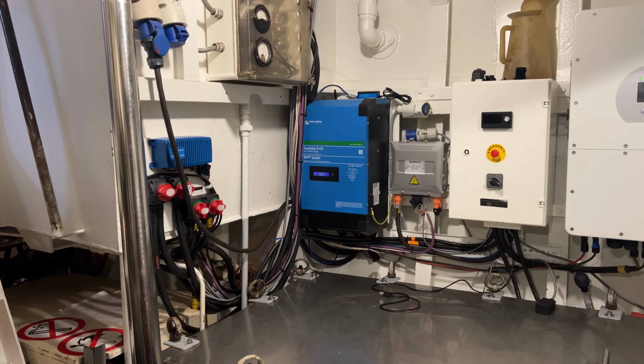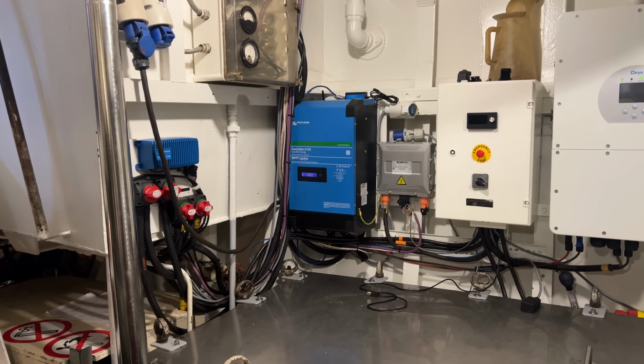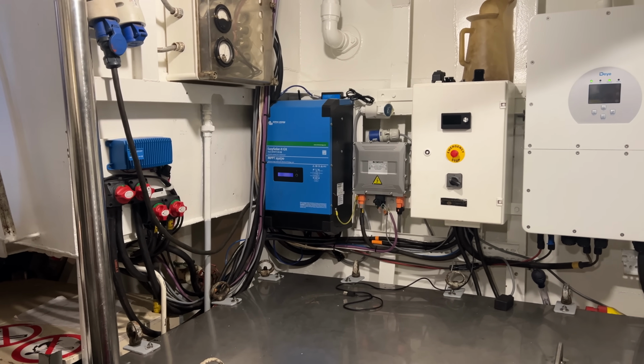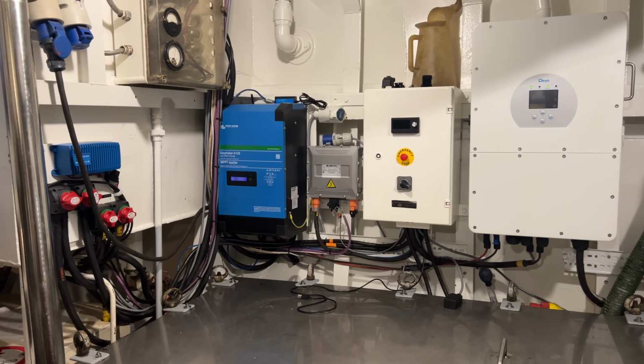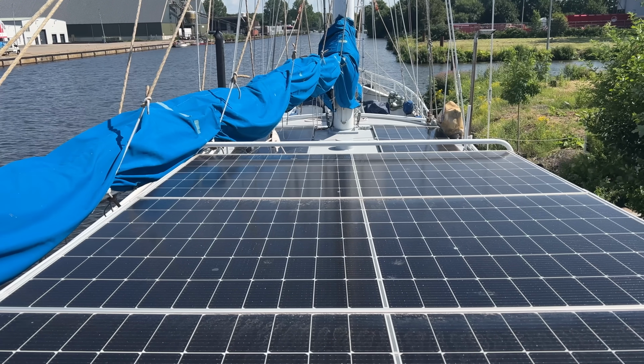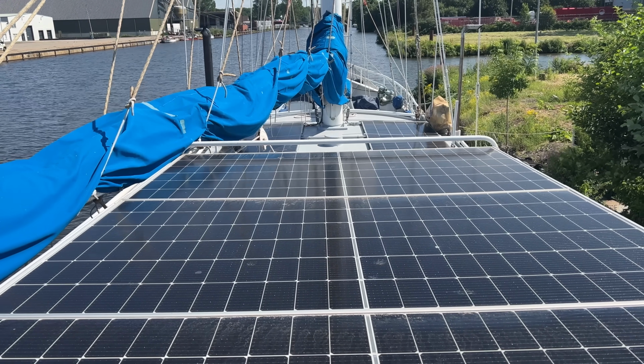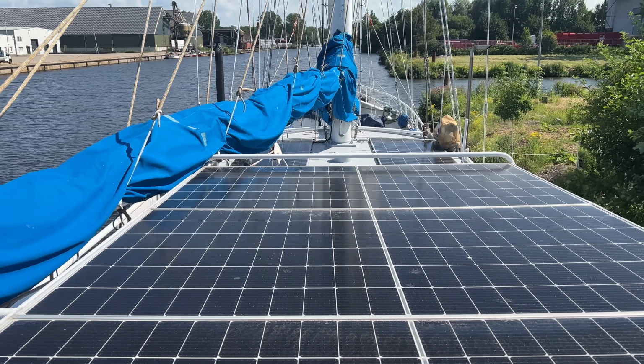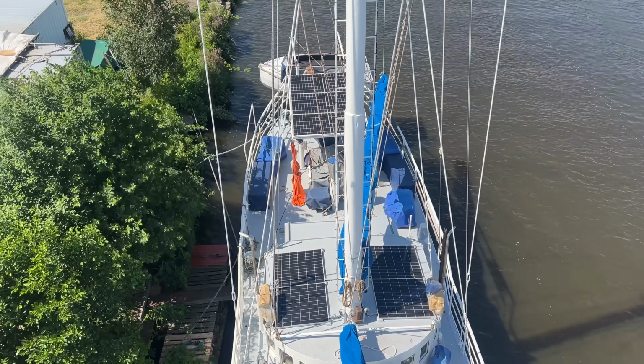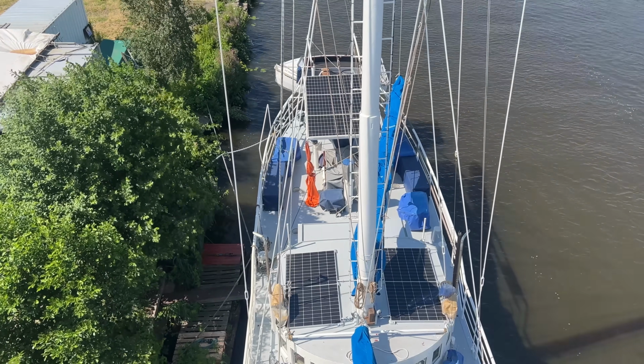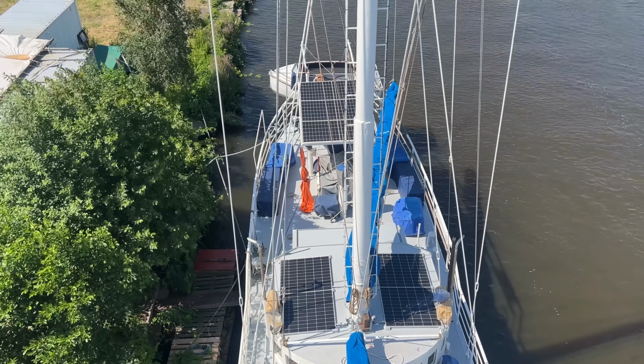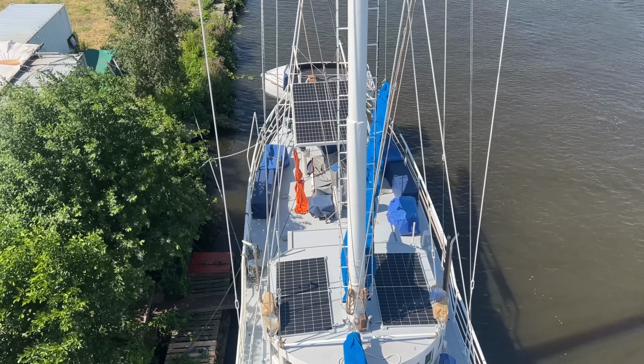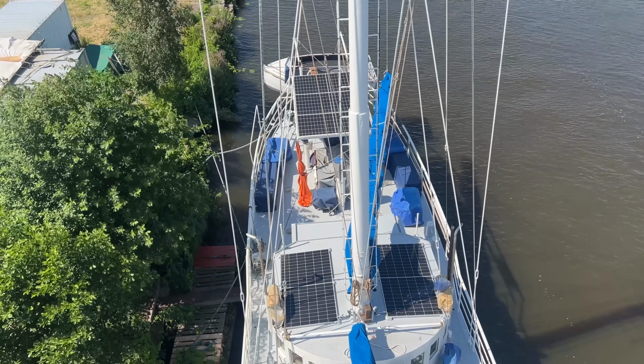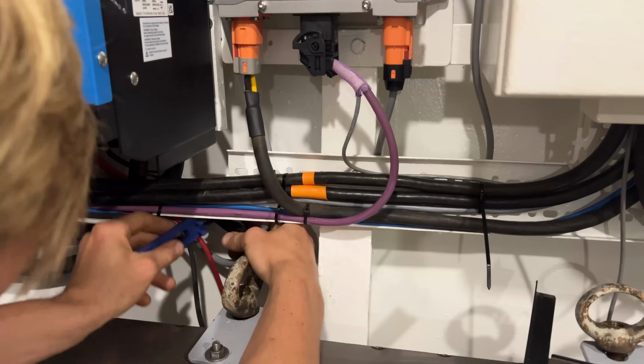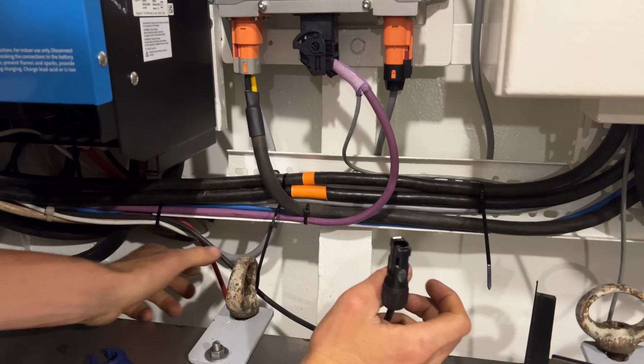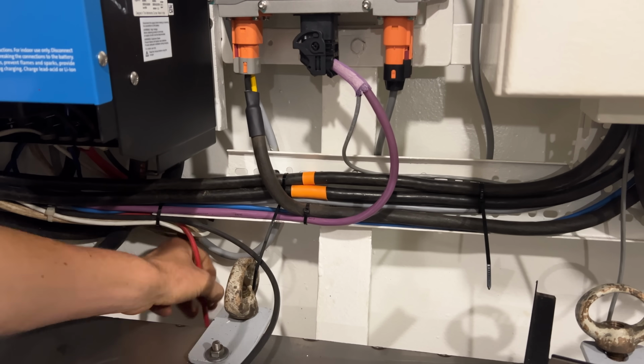But first I want to make sure the settings on our new hybrid inverter are correct, so that it does not overcharge or overdrain the batteries. The solar panels used to power our 24 volt hybrid inverter, charging the 24 volt batteries. But now the new high voltage battery will take over all the household equipment on board through the new inverter. So we'd rather have the solar panels charge the big battery and give the 24 volt one a small top up every now and then. With both inverters switched off, we can simply unplug the panels from the old one and plug them into the new one.